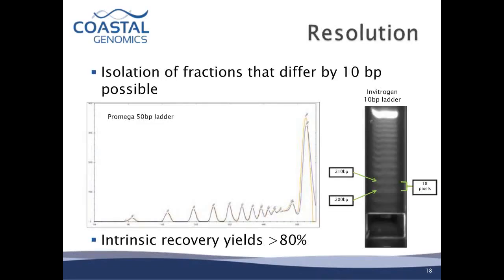Because the system uses long electrophoretic laneways, Ranger Technology achieves resolution on par with polyacrylamide gel size selection. Fragments differing by only 10 base pairs can be isolated and extracted from each other by the time they reach the extraction well — matching the resolution used by the University of Utah — and the system provides intrinsic recovery yields typically above 80% of the material within the target range.